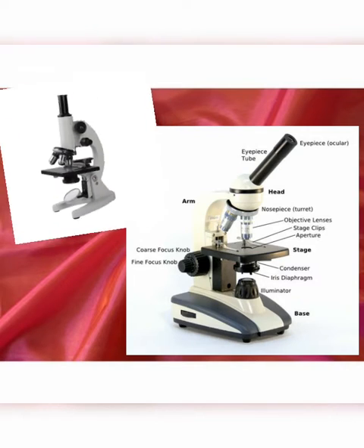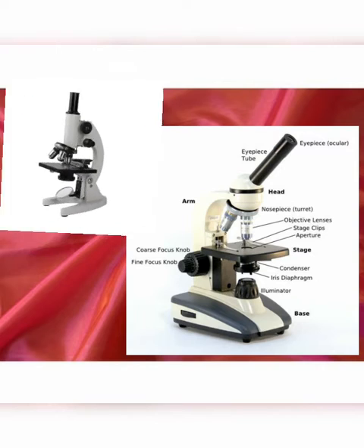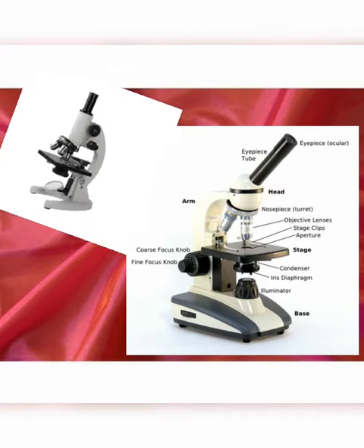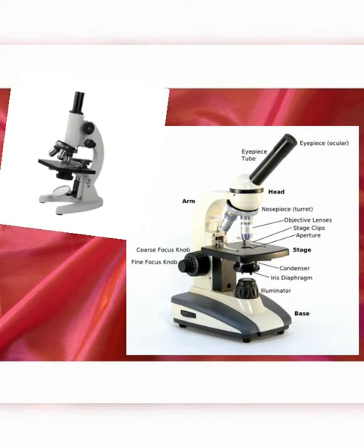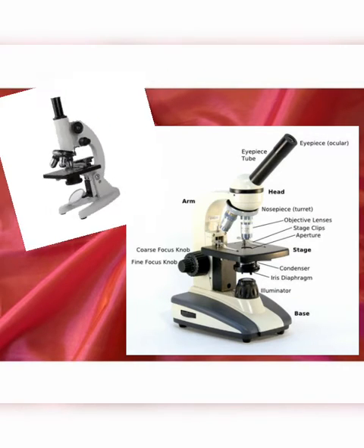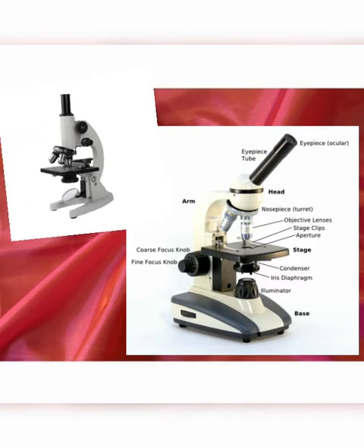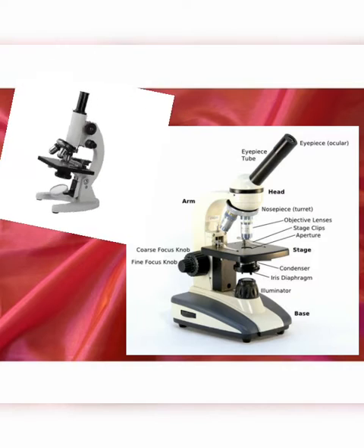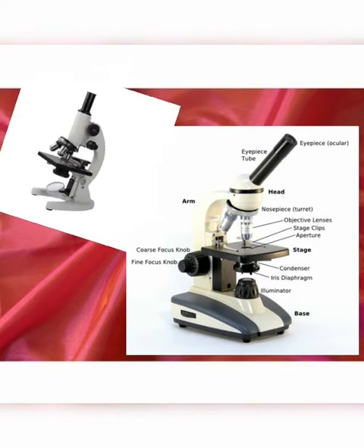Adjust the eyepiece and the objective lens in a line by rotating the nose piece. Always first use the lower power objective. Open the diaphragm of the condenser fully for passing the light on the stage. By using a coarse adjustment, raise the objective about 3/4 inch above the stage. Look through the eyepiece and tilt the mirror toward the light source. Adjust its position so that it reflects light upward through the hole in the stage. By doing this, you will get a bright, uniform illumination circular field in the microscope.